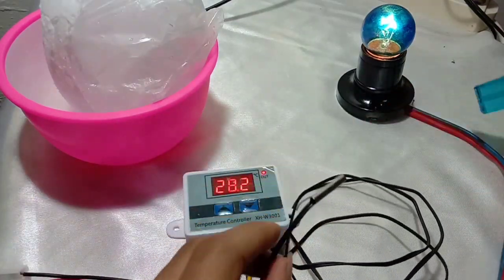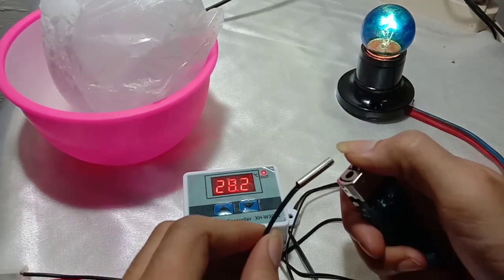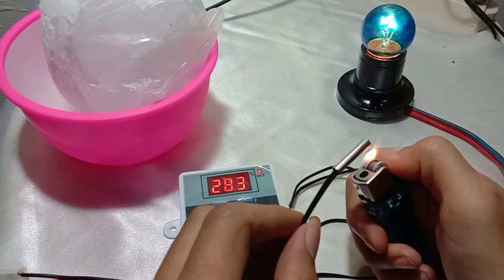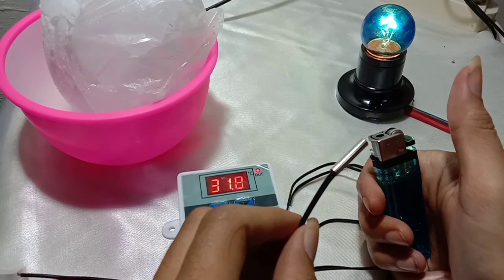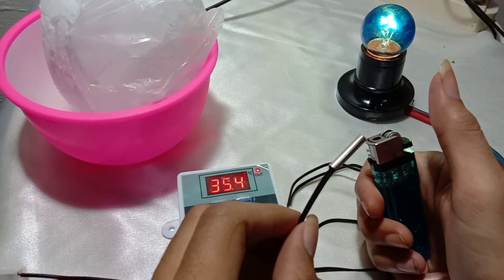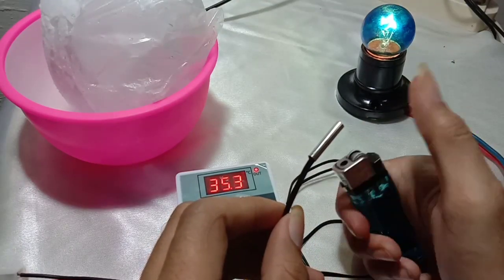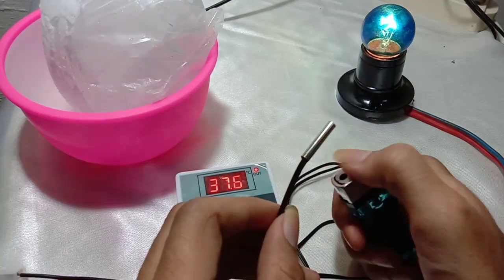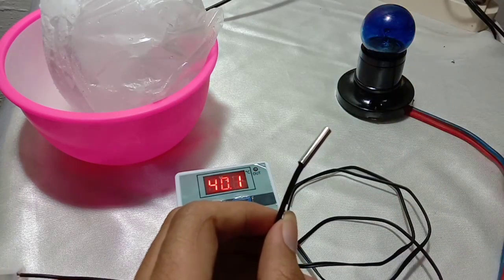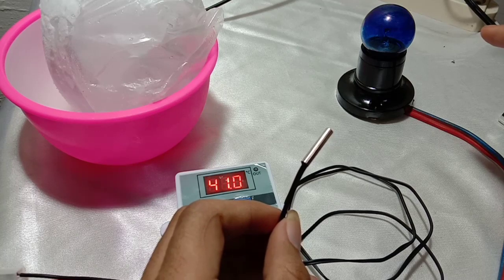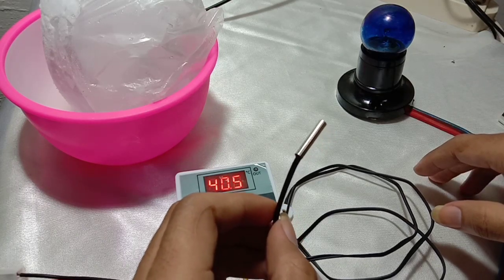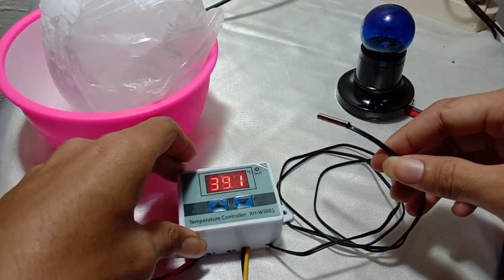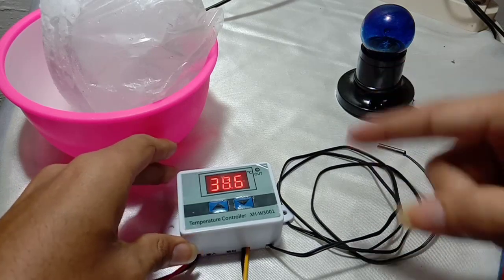If the temperature exceeds 38, the electricity will be disconnected. If the temperature is higher than 38, the electricity will be disconnected, and if it has come back to 37.5 it will be turned on for the second time.